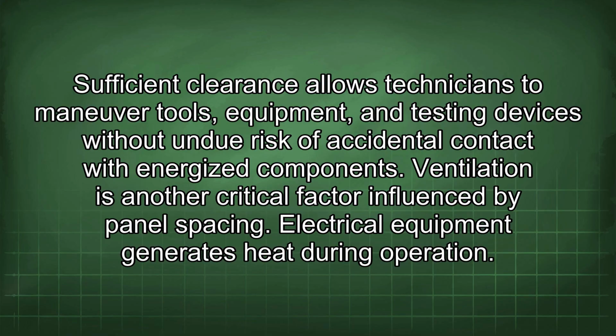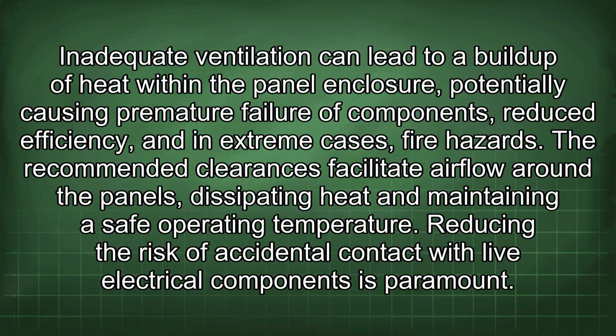Ventilation is another critical factor influenced by panel spacing. Electrical equipment generates heat during operation. Inadequate ventilation can lead to a buildup of heat within the panel enclosure, potentially causing premature failure of components, reduced efficiency, and in extreme cases, fire hazards. The recommended clearances facilitate airflow around the panels, dissipating heat and maintaining a safe operating temperature.